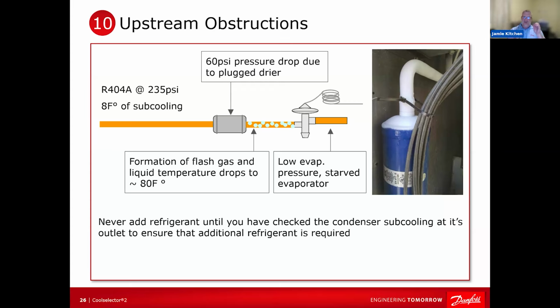So if your filter dryer is plugged, and trust me, when we size these things, unless you're way, way off, it's usually sized for 1 PSI or 1.5 at the most, usually less than that. So if you're measuring a 2 or 3 degree temperature difference across your dryer, right? And unless the connection is stepped down 2 sizes, that ain't the problem. It's plugged. Yeah. Now, whether it's plugged bad enough to want you to change it out, that's your call. Just remember, it's never going to get better, right? So maybe sometime when the system's down, change it, make a note, whatever. But again, that's just up to you. It's never going to get better.